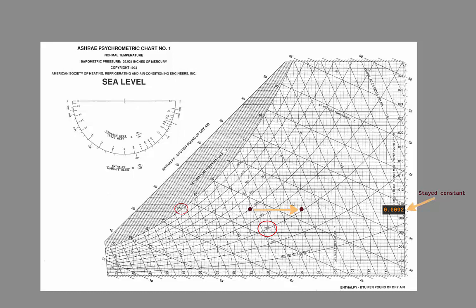Returning to the psychrometric chart one last time, there is also this property called enthalpy. That is the total heat or energy content of the air. It takes into account the dry bulb temperature of the air as well as how much moisture is in the air. There are times when it is important to measure such a value, in particular for some control strategies used in economizer cycles. Such control strategies will be discussed in the airside economizer cycles lesson in Module 2. In this lesson, we are only focusing on the sensor used in such a control loop.